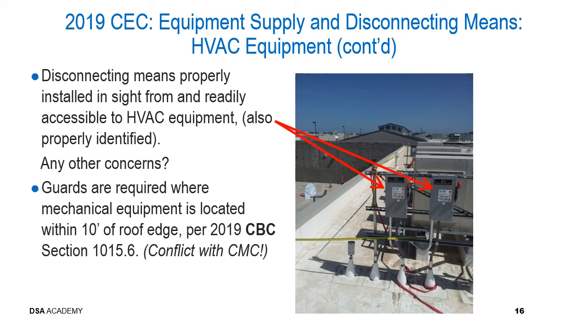And the answer is guards are required where mechanical equipment is located within 10 feet of the roof edge. And this requirement exists in the CBC, section 1015.6. And as we've discussed in other presentations, specifically the mechanical code presentations, this conflicts with the California Mechanical Code. The California Mechanical Code requires that guardrails are installed when equipment is within 6 feet of the edge of the roof. However, the 2019 version of the CBC, section 1015.6, is more restrictive in that it requires guardrails when equipment is installed within 10 feet of the roof edge.